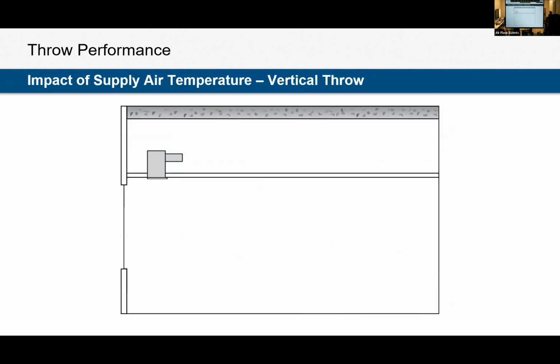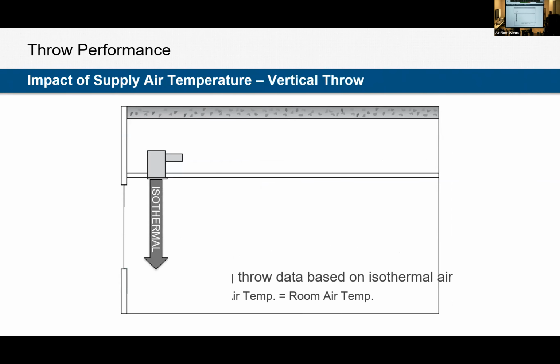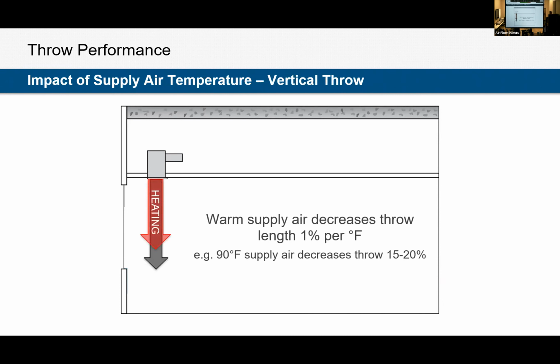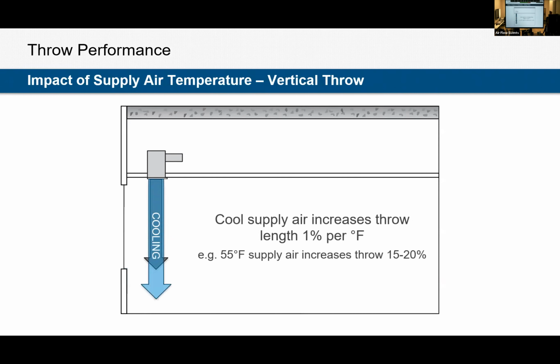The opposite is true if we are throwing vertically. Because in heating, again, our air wants to stay high and hug the ceiling. So in heating, we will get shorter throw distance compared to catalog. And in cooling, we will get longer. Cold air is heavy and likes to fall.